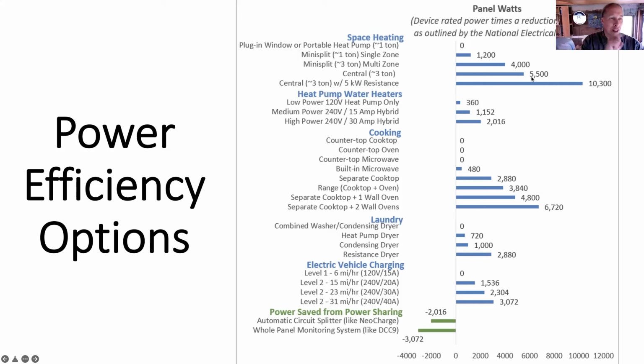What if you didn't get a cold climate heat pump and just used electric resistance? Below, say, 20 degrees or 10 degrees, as opposed to getting a negative 30 Fahrenheit-rated product, that electric resistance doubles the power demand. So in the commercial retrofit guide we're publishing, hopefully next month, we have a whole product guide for cold climate heat pumps of all types, package types, hydronic types, everything organized around its cold climate rating, so we can avoid this big hit on a building's power demand from using electric resistance when you could use a heat pump.